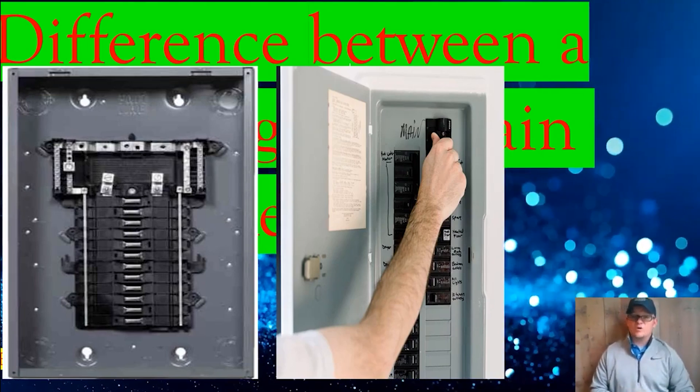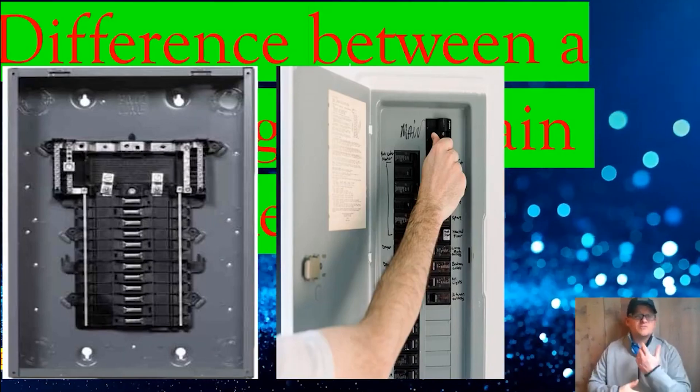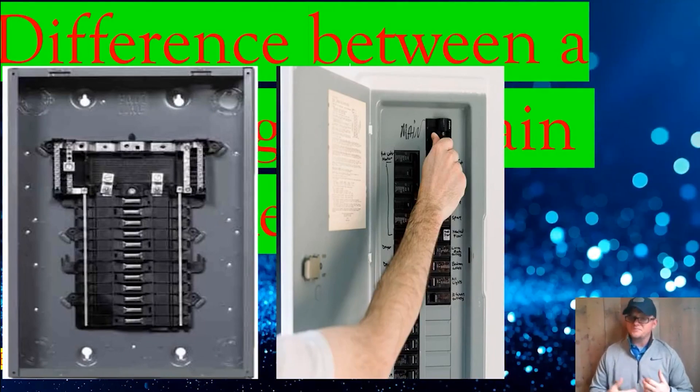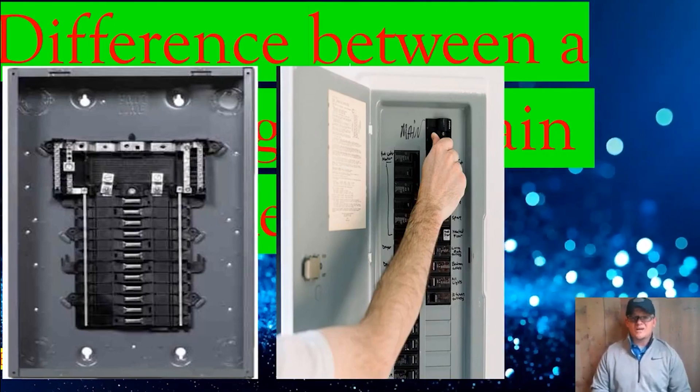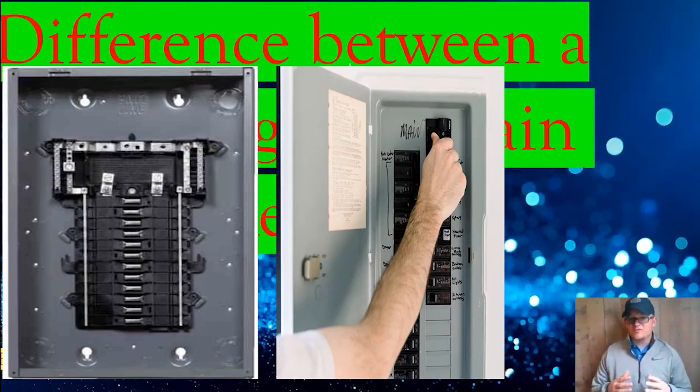Now this is going to be fed from somewhere else. So this panel, the first one that we saw here, is going to be fed from somewhere else that does have a breaker, but you don't have a breaker at that location. So if you went to work inside this panel and did not know that, you might not know that you can't shut this panel off until you took the cover off.